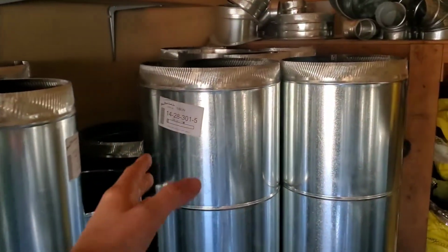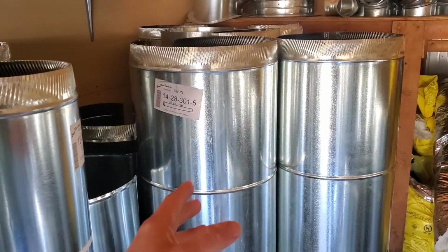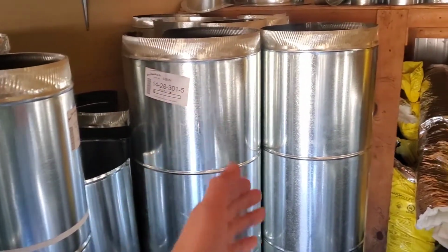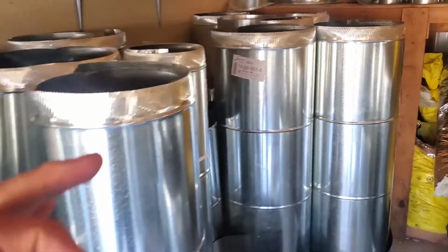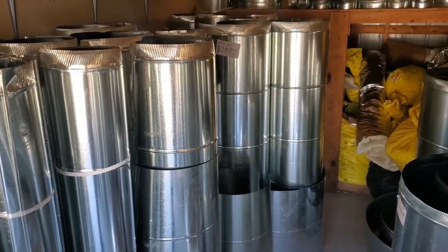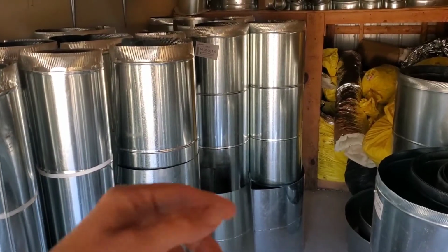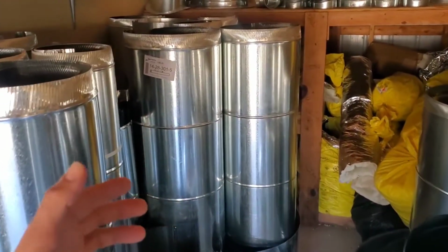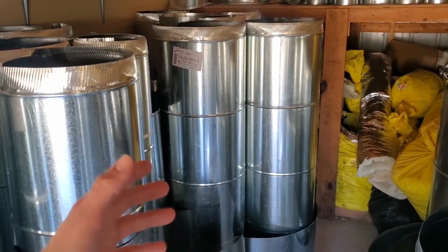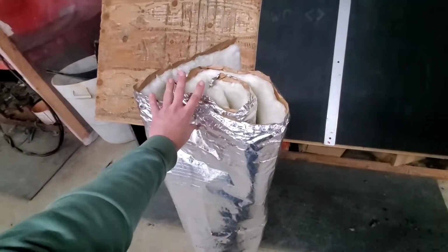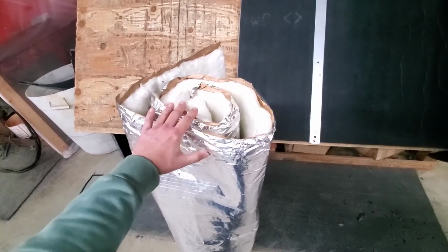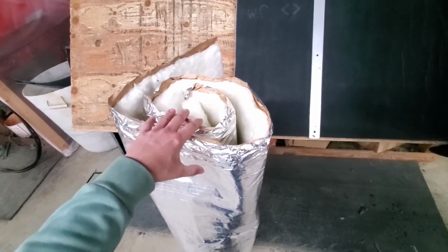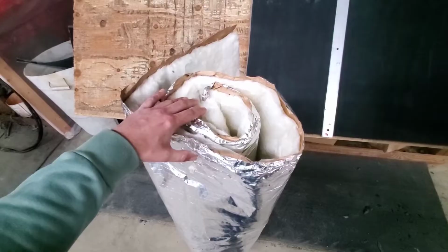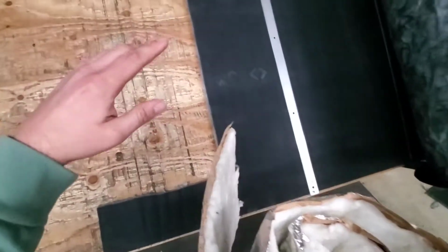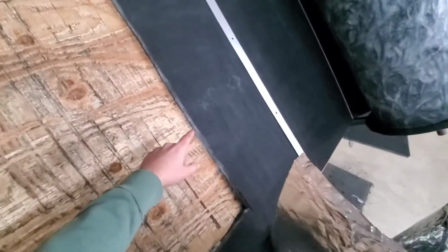And you would ask, what is better, Tad? Is rectangular ductwork better than round duct? Well, if you're looking for a more custom aesthetic job, I think that rectangular duct definitely looks better. If you're looking for a better sound, then, if you have liner on the inside of the duct, you're gonna have better sound. It's gonna be a little bit quieter. So if you have round duct, this is the insulation that's gonna be used as the wrap for that ductwork, okay? If you have round duct, you're using 3-inch wrap, okay?